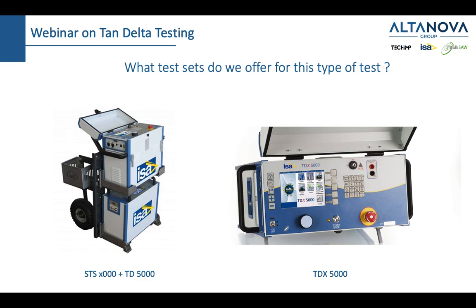What is the maximum testing voltage of a low voltage transformer? On the primary side, you would generate 10 kilovolt, and on the secondary, you would generate 0.4 kilovolt. And you will see that now. Is there any chance of a difference in the capacitance and tan delta measured from high to low, and low to high? They're absolutely the same. Whether you measure from the high voltage side or the low voltage side, the number should be the same.